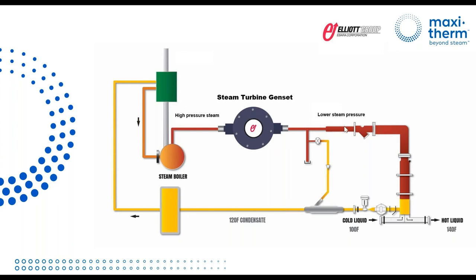Now, when you don't use a flooding design, typically a steam turbine will need about 4% more steam at the steam inlet to generate the right output. So 4% on top of the boiler efficiency, it's like 5-6%, but let's keep 4% more steam. When you use a flooding design, you will need 6% less steam minimum, and I'll show you numbers today, to generate the hot water you need here. So 4% more, 6% less, well, it's more than break even. This is why it's a great combination, using a steam turbine with the flooding design.